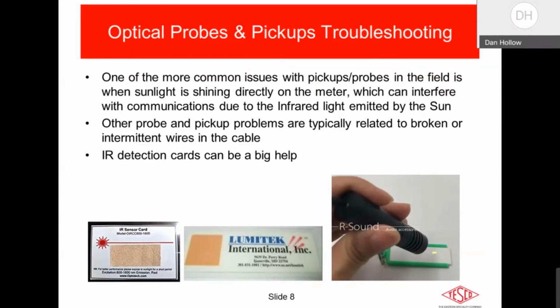So there are a lot of things that go into communicating optically with a meter that need to be taken into consideration. One of the ways to really find out what's going on, and I used to use these many, many years ago, it's been a long time, maybe 25 years or so since I've used these little things you see at the bottom. Sunlight is also a big problem. But what these little cards at the bottom do is detect infrared light, which is not visible to the human eye. But one of the common issues I hear a lot of in the field is somebody goes out there with a field test kit with an optical pickup, or they go out there with their laptop or their handheld and an optical probe connected to it, and they want to communicate with the meter, they want to read the meter, they want to reprogram the meter, and the sunshine is directly overhead, and it's just beaming right down on that meter at the right position.